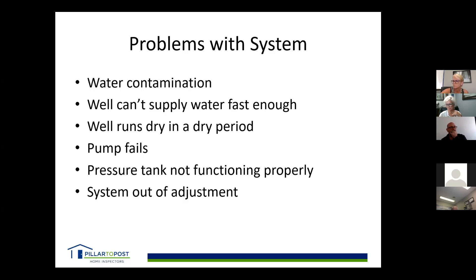Well water can run dry during long dry periods when rain isn't refilling the well fast enough. Pump failure is another common issue — pumps run to failure since they're hard to maintain at the bottom of the well. Pumps aren't that expensive — about $1,500 to $2,500 — but the labor to pull 200 feet of pipe and power cable is significant and requires a professional.